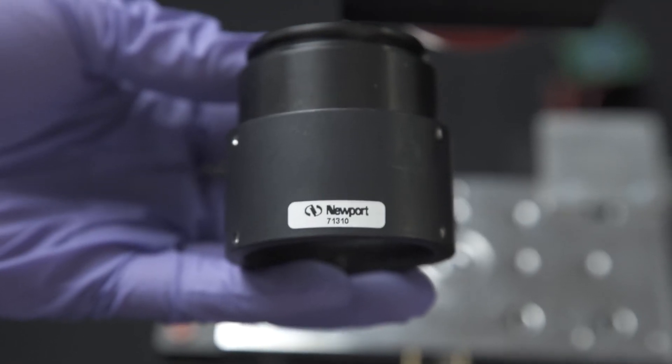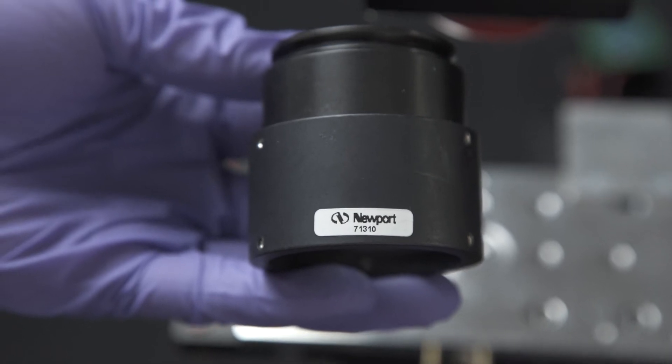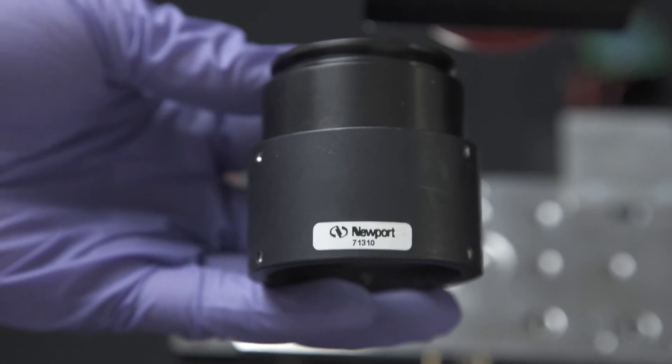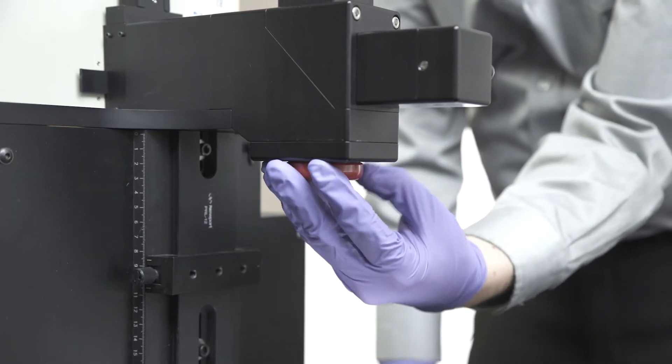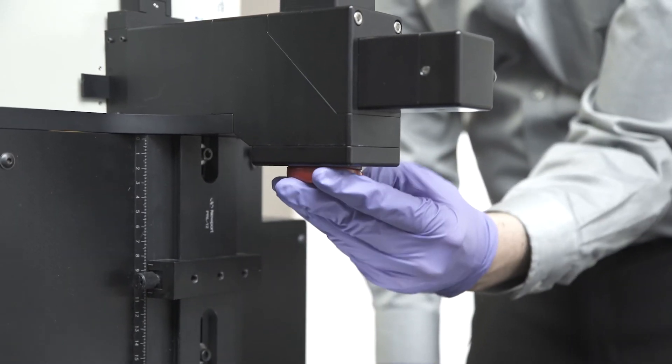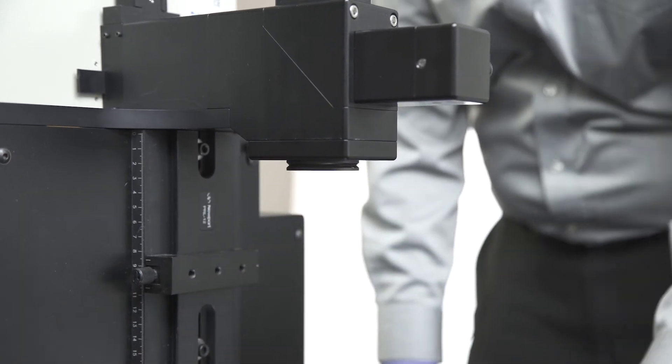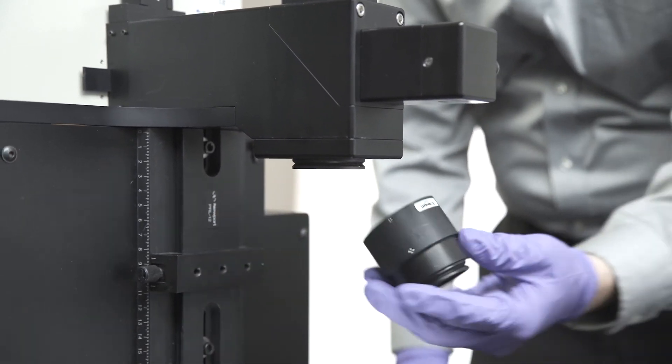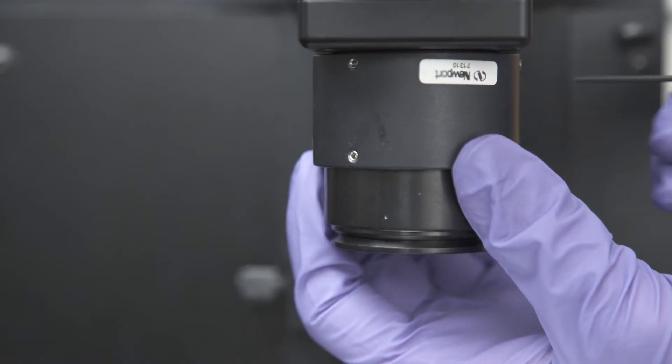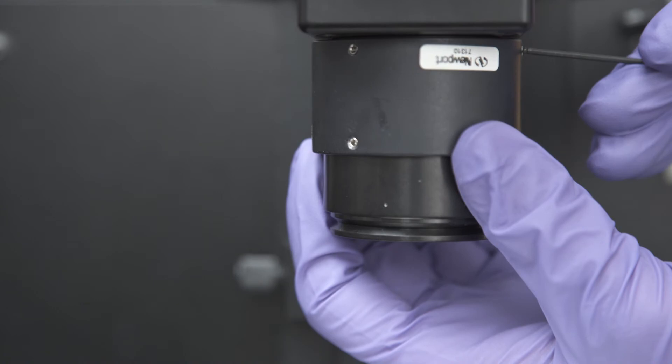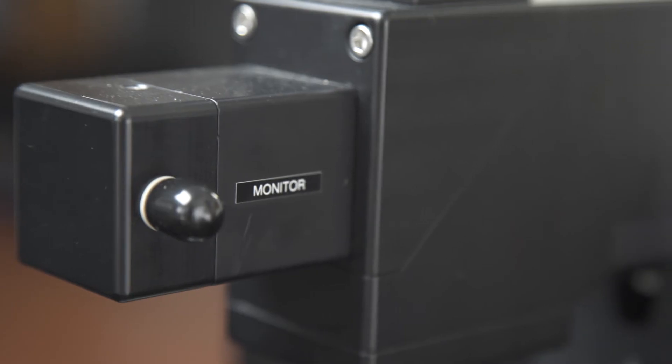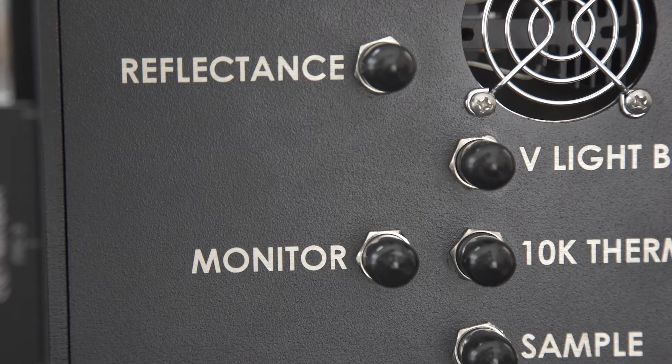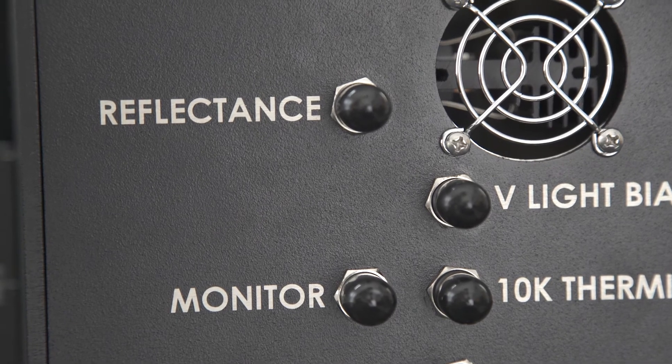Secure the light shield, part number 71310, to the output port of the optical assembly. Next, we connect all the cables to the correct ports as detailed in the user manual.